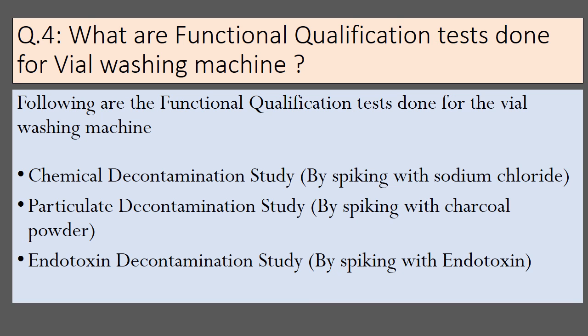The next question is: what are the functional qualification tests done for a vial washing machine? The following are the functional qualification tests: first, chemical decontamination study by spiking with sodium chloride; second, particulate decontamination study by spiking with charcoal powder; and third, endotoxin decontamination study by spiking with endotoxins.